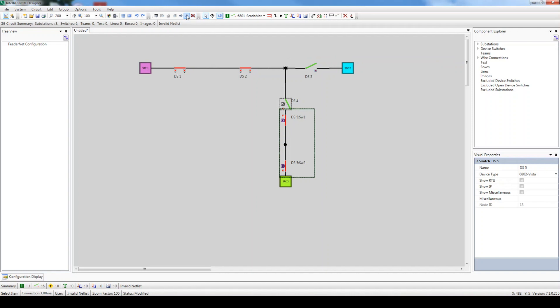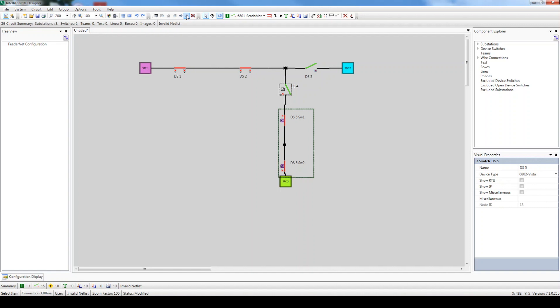For normally closed switches next to the source, we recommend placing the X terminal of the Intelliruptor switch, if configured for Direction 1, facing the normal source, which is the case for DS1. Also, for non-Intelliruptor switches next to the source, such as DS5, the sensor side terminal should face the normal source, which is the case here. For all other normally closed switches, the sensor location doesn't matter as long as it matches what's installed in the field.